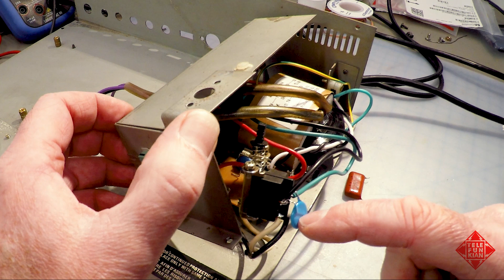I've put another safety capacitor after the switch—this one before the switch, and this one after. This may cut down on the arcing inside the switch, which contributed to its failure, one of the reasons why this instrument wouldn't turn on at all prior to our repairs.